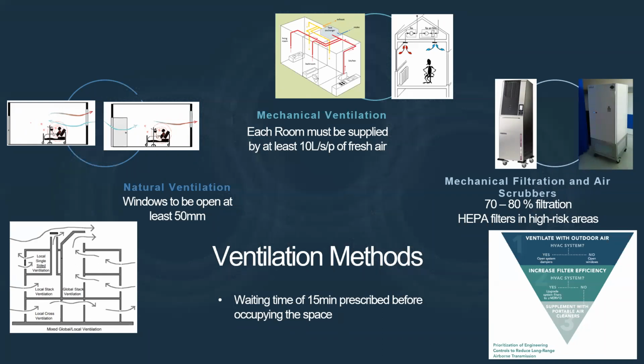Then lastly, I just would like to show you the controls to reduce the long-range airborne transmission criteria, and we are using this in our ventilation audits that we have done, and we will discuss that also in the next slide. When we evaluate the outdoor air ventilation system, if we have a ventilation system, we make sure that the dampers, as they call it, are fully open, or the air speed of the fan is opened up fully so that you have 100% discharge of fresh air into the area.